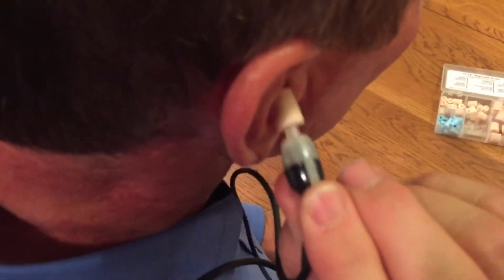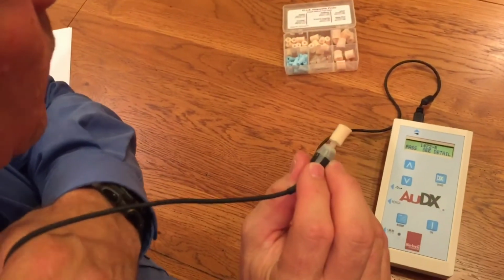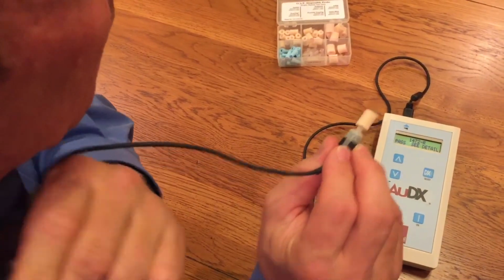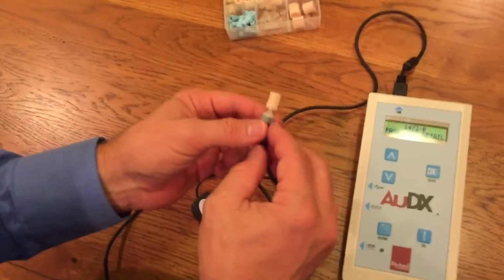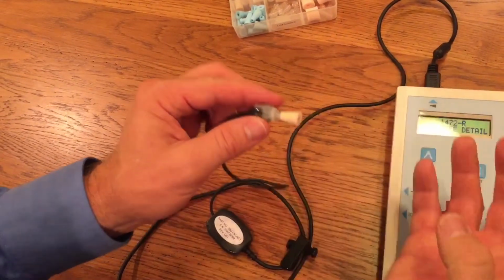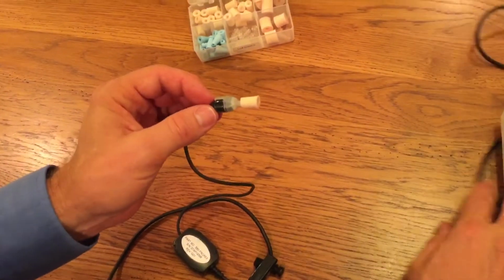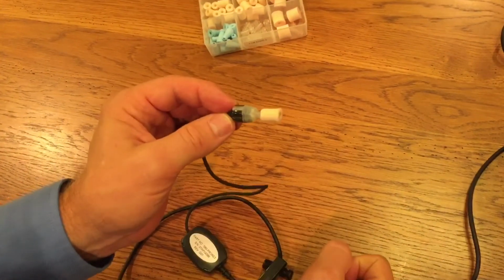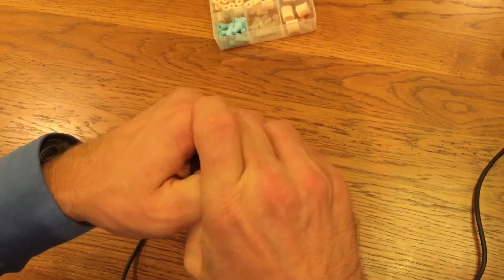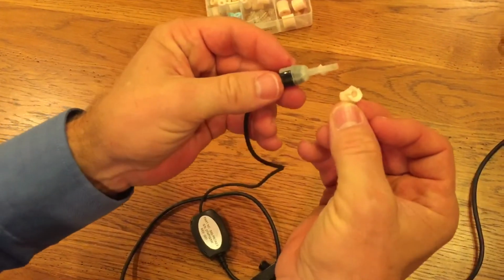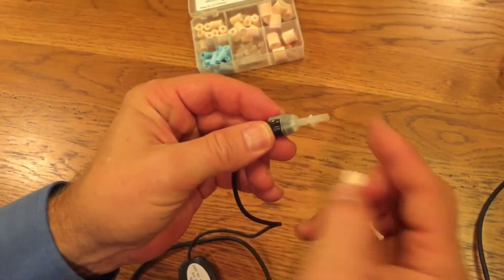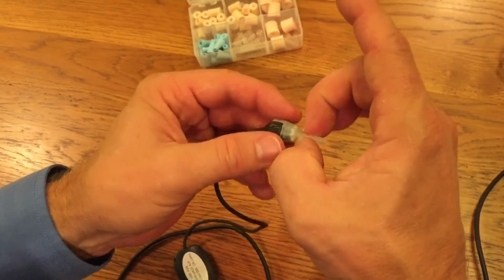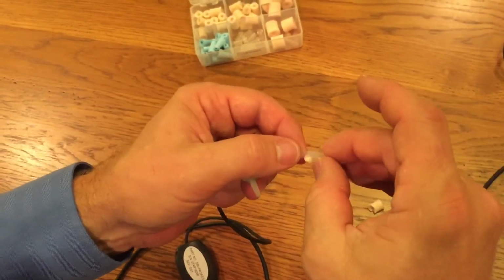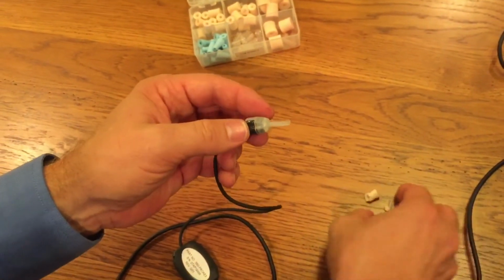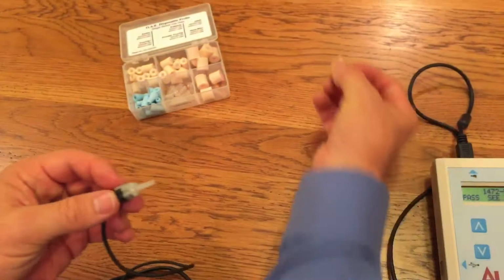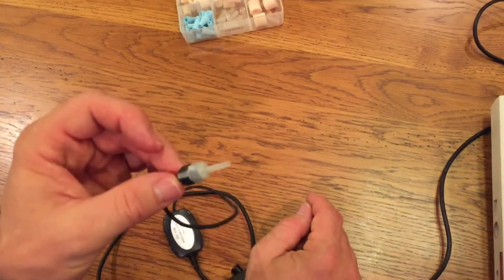So when you remove the probe, remember that the probe can be used on the same child for both ears, but it's disposable and should never be used for multiple children or used on different children. Now with this particular piece of equipment, occasionally the little plastic sleeve will stay on. So if we pull it off, and here the foam came off and the plastic has stayed on. So we recommend that you use your fingernails and you actually pull it so that the plastic sleeve is removed and the whole probe is removed. You will want to dispose of used probe covers and use a new one with every child.